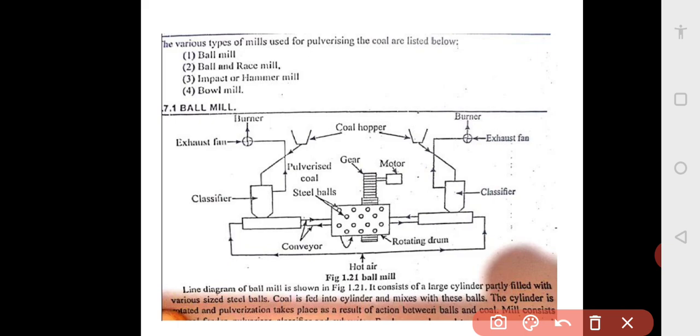The oversize particles are thrown out of the air stream in the classifier, and the fine material is passed to the burner through the exhaust fan. The output of the mill is controlled by dampers located at the exhaust fan inlet duct. These dampers vary the flow of air through the mill and thereby control the rate of fuel removed.